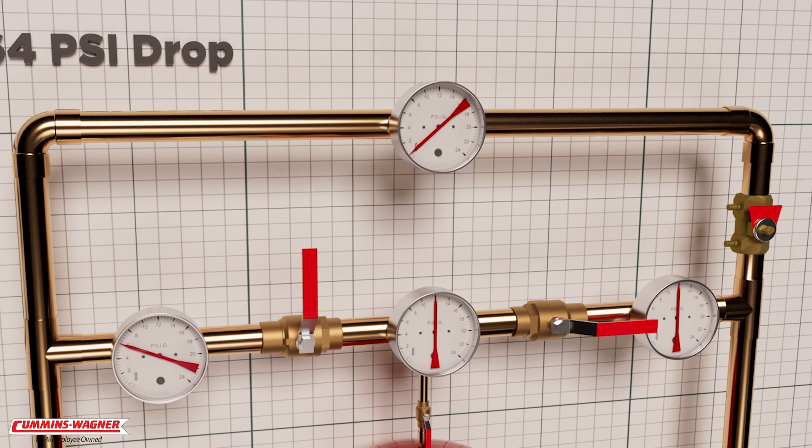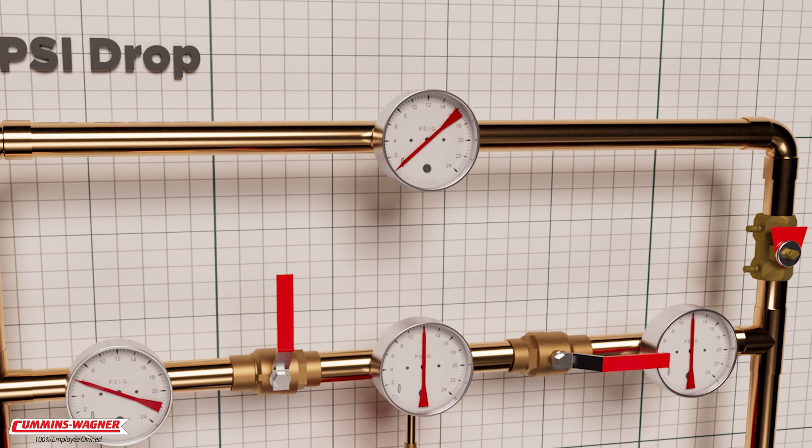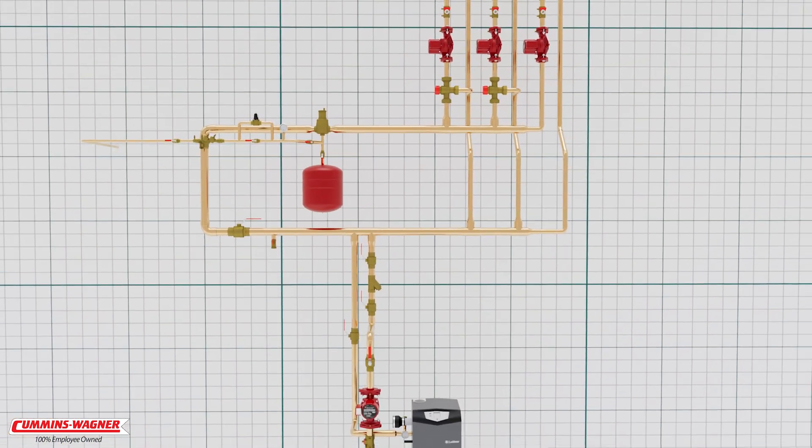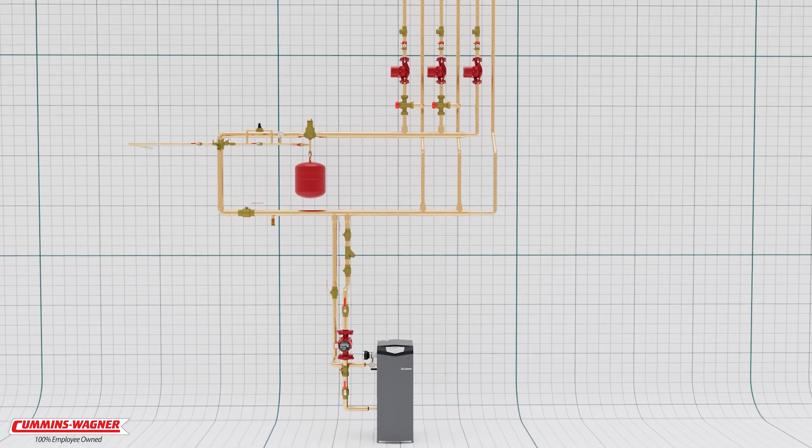Not only will we have no flow at the top of the system, but we could even pull air into the system through our air vents. This is why we always pump away from the expansion tank, or the point of no pressure change.